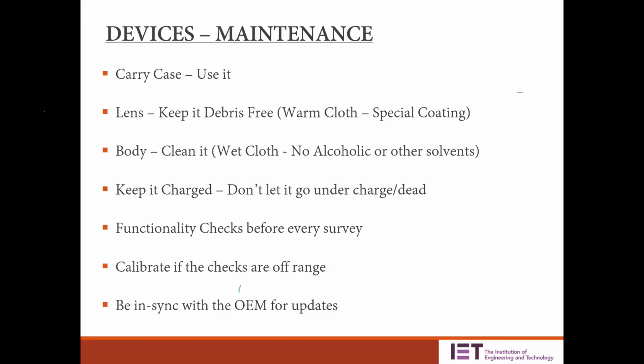For functionality checks, you can measure boiling water, melting ice, and the tear duct temperature of someone nearby to check whether the readings are within range. If the checks are off—for example, if boiling water reads around 50 degrees—that tells you your camera's calibration is well off. It's time to send your camera to the manufacturer for calibration checks. They will fix and calibrate it and send it back. That's how you know whether calibration is required.